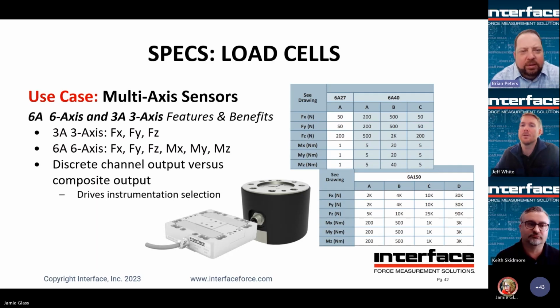Yeah, so in terms of specs, it's good to note how symmetric the multi-axes are that you're looking for. With 3 axes, they're discrete, meaning you can think of it as 3 individual axes or 3 individual sensors, all giving you isolated output for each axis. Whereas the 6 axis, as Jeff mentioned, outputs 6 channels' worth of data, and thus the instrumentation is really important to be able to calculate the individual axis-specific output. That's how these load cells are calibrated, and they're anticipated to be used with that.